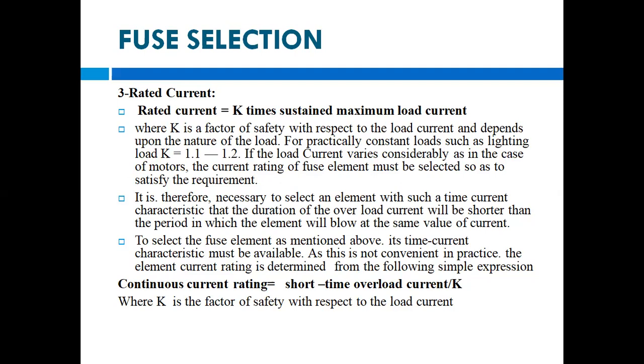So K times the sustained maximum load current means when you are connecting the maximum load to the circuit, whatever current flows through the circuit should be borne by that fuse, and that is K times. Here K is the factor of safety, and it depends upon the nature of the load.